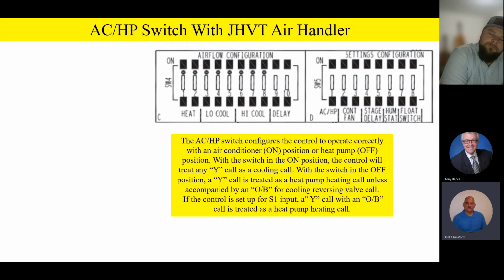Any questions or comments on that? Like I said, we've got to really wrap our noodle around that. So there's a couple things the contractor is going to have to do when they set this air handler up. It has to have the HP switch in the heat pump position. They're going to have to configure the board for that S1 input.